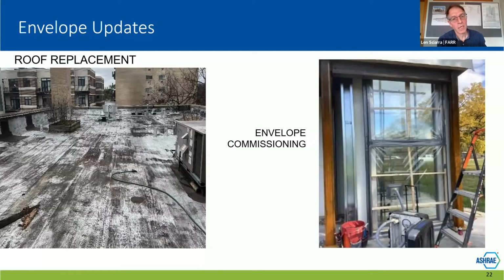So what we did is, if you look at all the sections, there's now a 9.1 section, like 5.9.1, 6.9.1, which has all the testing requirements, the functional testing that a manufacturer or subcontractor would do. Then the next level, for larger buildings and larger systems, is systems commissioning, which is all under the 9.2 section, so 5.9.2, 6.9.2, 7.9.2.